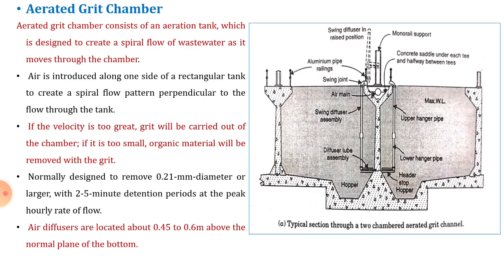The aerated grit chamber consists of an aeration tank. Air is supplied in the grit chamber, which is designed to create a spiral flow of wastewater as it moves through the chamber. The air is introduced along one side of the rectangular tank to create a spiral flow pattern perpendicular to the flow through the tank. As seen in the figure, the air main is provided at the center; hoppers are at the bottom of the tank and a slope is provided so that particles will settle and slide into the hopper.